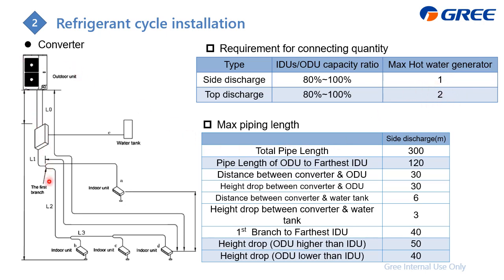And here is the total piping, which is the max piping length. It is the limit for when you adopt the converter. This one connects with the water tank, and this is for the indoor units. So the total piping length can be up to 300 meters, and from the outdoor unit to the furthest indoor unit it is the same as the regular heat pump, which is the GMV Mini, 120. For the other limits, just follow this table to finish the installation.